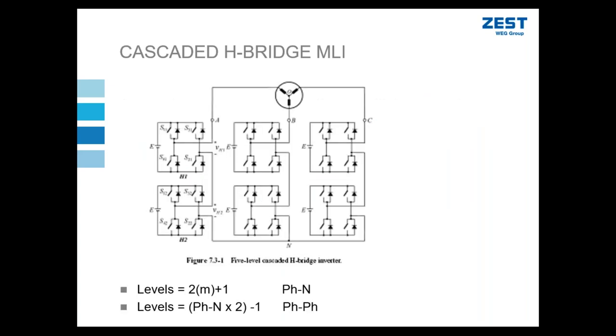All right, let's first examine how we define this drive in terms of the number of levels. You saw previously that a 3.3 kV drive needs three power cells per phase. I'm just showing a simplified example of a drive that would theoretically have two power cells per phase, six power cells in total. The way that we determine the output level per phase, phase to neutral, as well as the output voltage phase to phase in these drives, is given by the formulas below.